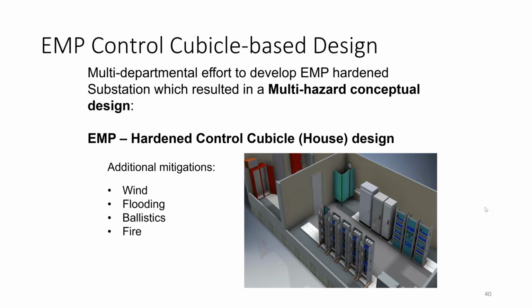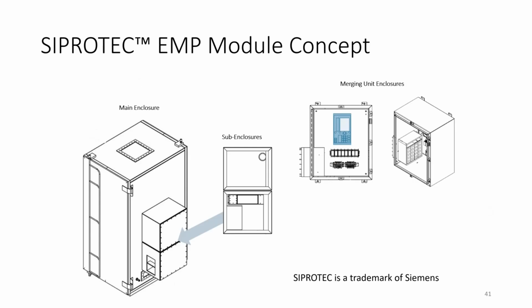So that shifted to a more modular approach that you'll see on the next slide, which is much more compact. It allows us to use a digital substation solution, as Frank mentioned. So we've translated everything that we were doing with metallic conductors into fiber optic cables. That really decouples what's happening in the yard versus the equipment that's housed inside the substation control house. So the module that you see here on the left is the main module, which houses the protective relays, the SCADA systems, telecommunications equipment, etc.